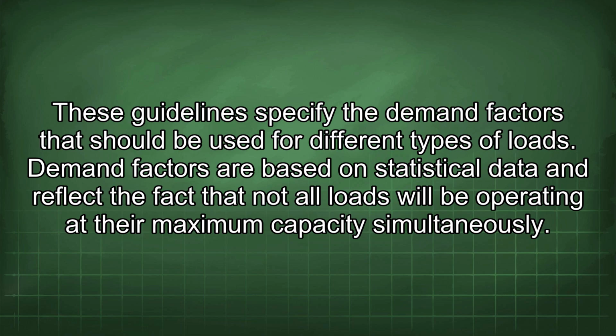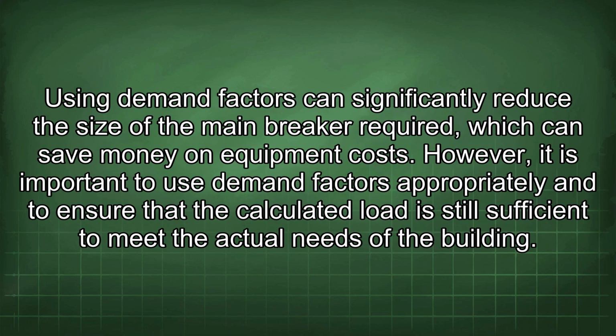Demand factors are based on statistical data and reflect the fact that not all loads will be operating at their maximum capacity simultaneously. Using demand factors can significantly reduce the size of the main breaker required, which can save money on equipment costs. However, it is important to use demand factors appropriately and to ensure that the calculated load is still sufficient to meet the actual needs of the building.